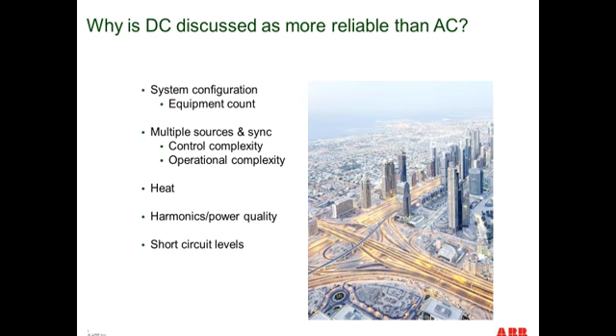A grid-to-chip design, as it's often called, can offer an owner benefits. For example, an IEEE 519 compliant design would mean no harmonics or filters to degrade the efficiency in the system. And the utility would potentially see no reactive power entering their system.